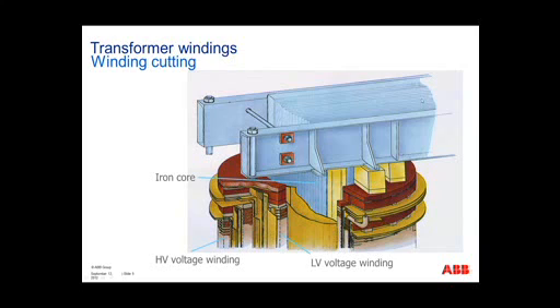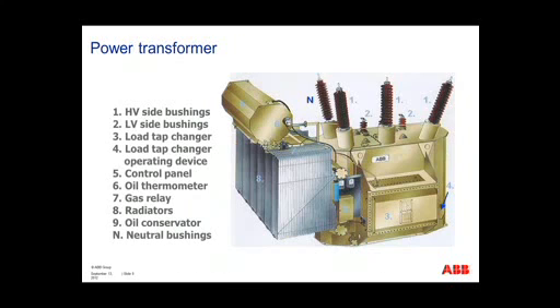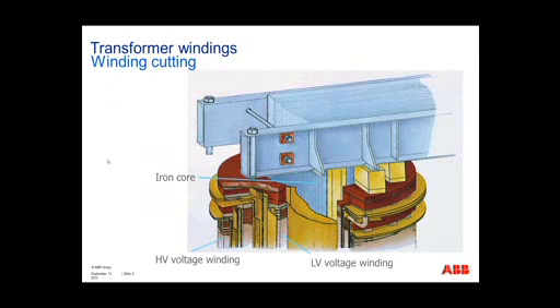Looking inside the tank of the core, we've essentially cut the transformer in half. Inside, we're looking at the iron core, and surrounding that iron core, we're going to have windings. The iron core, keep in mind, is at ground potential. Typically this core is laminated, and it's laminated on multiple levels. This lamination helps keep the eddy currents in check. The less eddy currents, the less losses you'll have in the transformer.